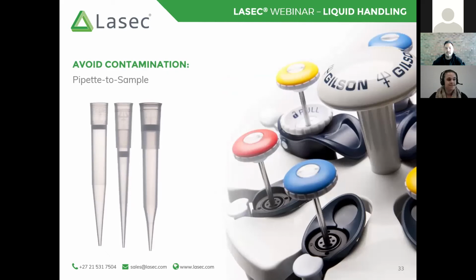So just quickly about contamination and the different types of contamination that you might find with using pipettes. The first one is pipette to sample contamination. This generally happens over time or by misuse of a pipette by an individual, or in instances where filter tips aren't used. So there's no physical barrier. What often happens is that sample gets into the pipette and over time either causes corrosion or buildup of other substances inside that tip holder. As you then pipette, inside that tip holder there's a piston that is moving up and down. It risks dislodging anything that has been stuck to the inside of that tip holder. If you're not using a filter tip, you risk that being expelled. Obviously, you are blowing air in an air displacement pipette, so you risk expelling that contaminant into your sample.